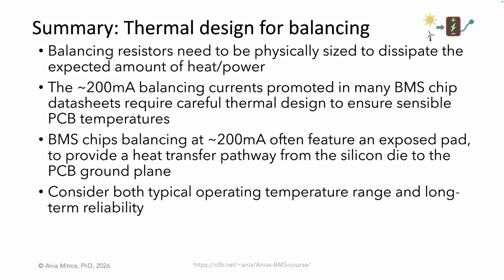Let's summarize what we've learned about the thermal design of balancing circuits. Balancing resistors need to be physically sized to dissipate the expected amount of heat or power. The roughly 200 milliamp balancing currents promoted in many BMS chip datasheets require careful thermal design to ensure sensible PCB temperatures. BMS chips balancing at about 200 milliamps often feature an exposed pad to provide a heat transfer pathway from the silicon die to the PCB ground plane. Consider both typical operating temperature range and long-term reliability.